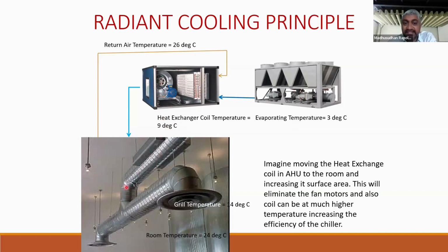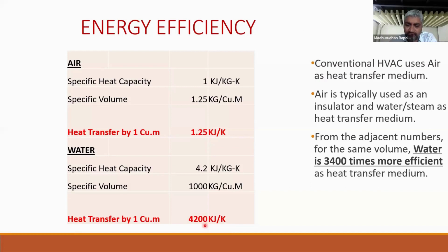Also, the coil doesn't need to be that cold now that the surface area has increased so much, and can be at a higher temperature. So that's why in radiant cooling we typically use chilled water temperature at anywhere between 16 to 18 degrees centigrade, which leads to better performance by the chiller, at least by 30% or so. But you still are able to get 24 degrees centigrade room temperature. So this is what allows lower energy consumption.